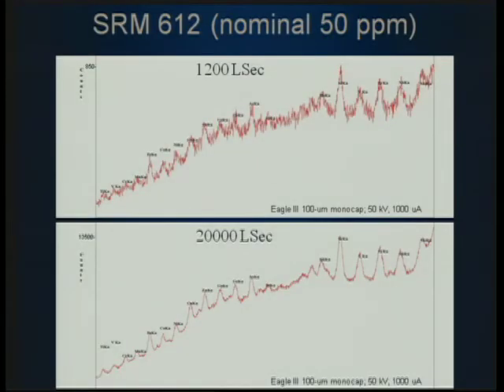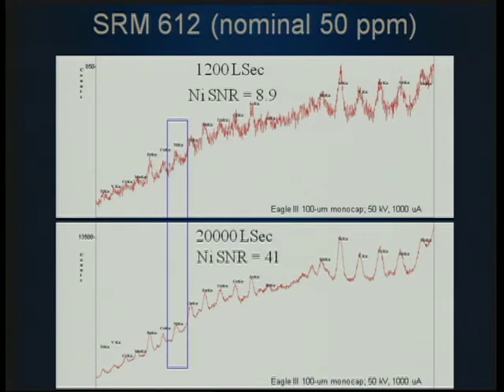Here's an example of SRM 612 with that variety of elements. The top spectrum was collected for 1200 live seconds, the bottom for 20,000. Just by increasing collection time you can greatly increase your signal-to-noise ratio. At 1200 live seconds the signal-to-noise ratio was 8.9, so collecting for 1500 or 2,000 live seconds would most likely have hit the target SNR of 10 needed for initial instrument method parameters.